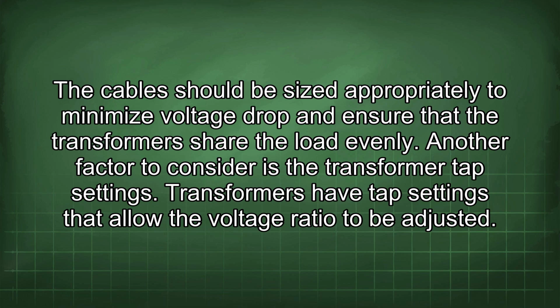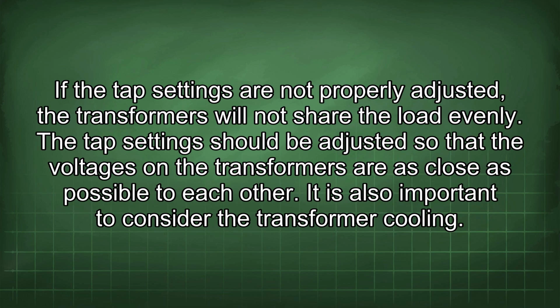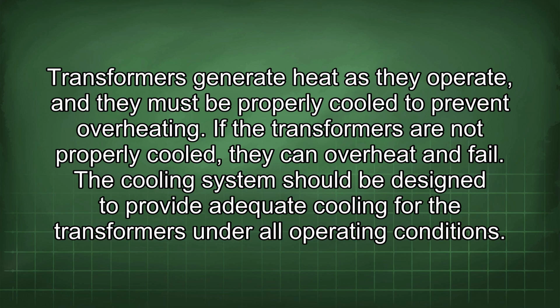Another factor to consider is the transformer tap settings. Transformers have tap settings that allow the voltage ratio to be adjusted. If the tap settings are not properly adjusted, the transformers will not share the load evenly. The tap settings should be adjusted so that the voltages on the transformers are as close as possible to each other. It is also important to consider the transformer cooling. Transformers generate heat as they operate, and they must be properly cooled to prevent overheating. If the transformers are not properly cooled, they can overheat and fail. The cooling system should be designed to provide adequate cooling for the transformers under all operating conditions.